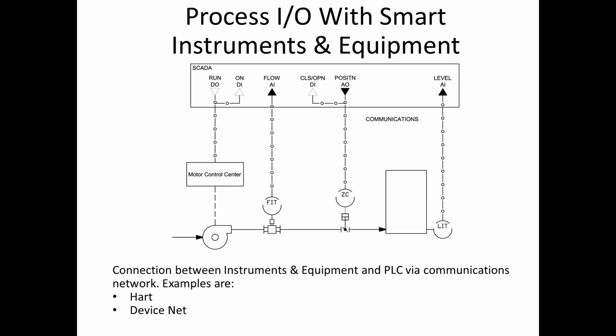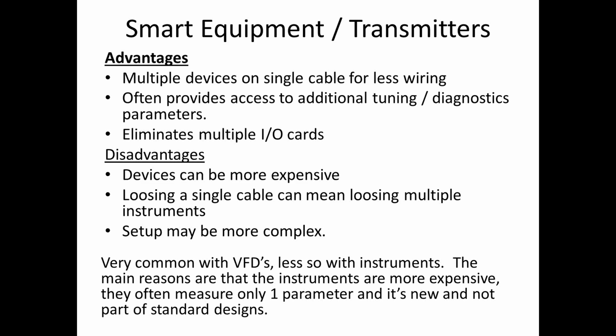And it's a more sophisticated method of communicating with the PLCs, not widely implemented at this time, but becoming more and more prevalent as time goes on. There are some advantages to using smart equipment. You can transmit multiple devices using a single wire, so you can use less wiring. You don't need those multiple I/O cards, and it often provides access to additional information that you can use for tuning and diagnostics.